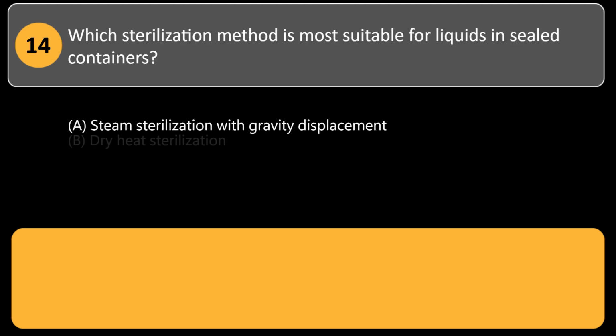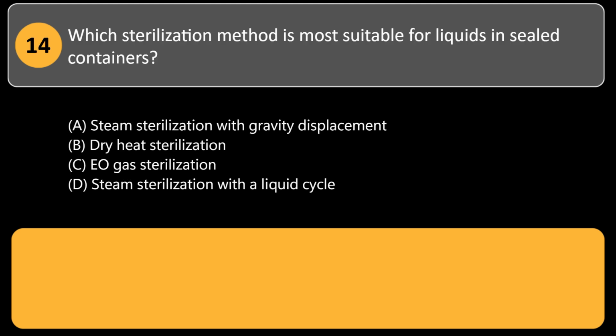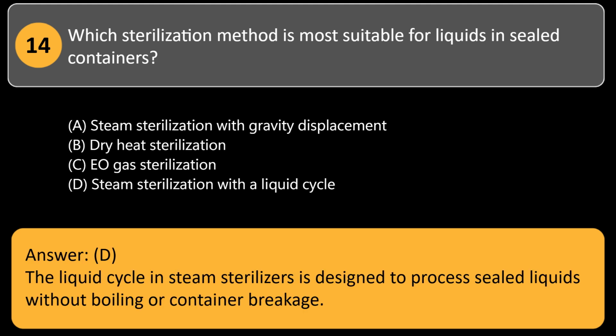Which sterilization method is most suitable for liquids in sealed containers? A. Steam sterilization with gravity displacement. B. Dry heat sterilization. C. EO gas sterilization. D. Steam sterilization with a liquid cycle. Answer: D. The liquid cycle in steam sterilizers is designed to process sealed liquids without boiling or container breakage.